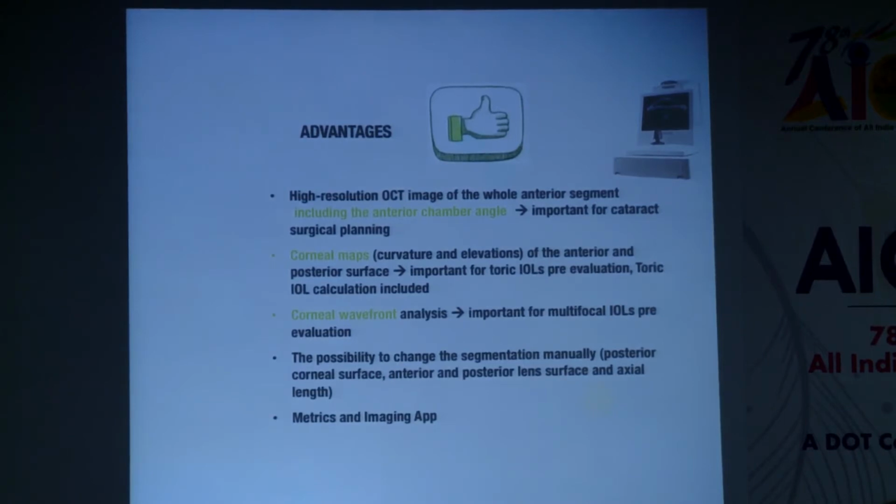The corneal maps give us the curvature and elevations of the anterior and posterior surface, which is important for toric pre-evaluation and toric IOL calculations. The corneal wavefront analysis is important for the multifocal IOLs pre-evaluation. The possibility to change the segmentation manually from posterior corneal surface, anterior and posterior lens surface is also there, and it gives us the metric and imaging app.